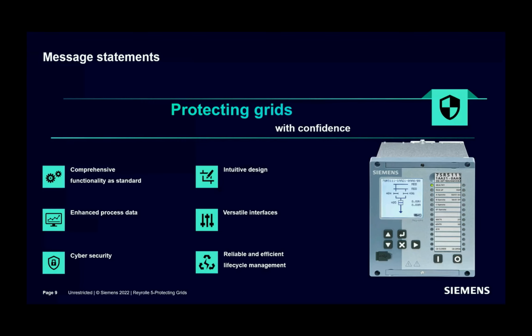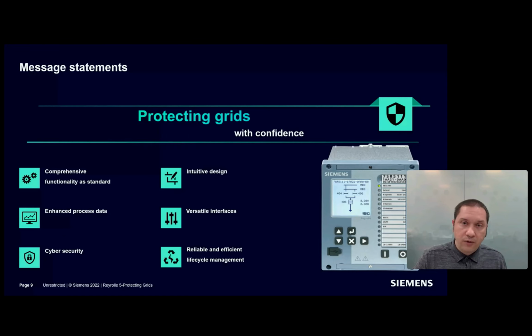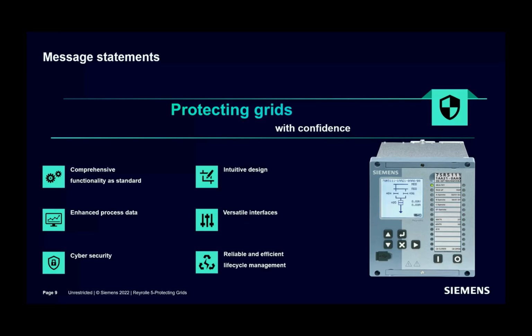Even further, Reyrolle 5 has withdrawable construction concept as a tradition for an easy product replacement. So not only Reyrolle 5, but also all the other Reyrolle portfolio since the beginning actually have withdrawable construction. And we tried our best to keep the device variants at minimum. As a result, current and voltage transformer inputs, power supply units, and binary inputs cover the full operating range. All binary input thresholds can be configured individually.